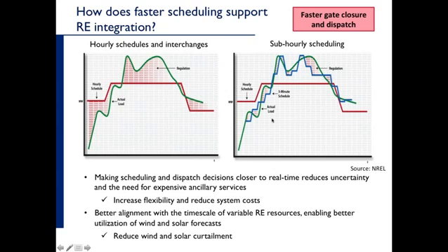Well, typically, the 5-minute economic dispatch is based on a forecast of the middle point of the 5-minute time period. And we talked through that on the timeline a few minutes ago. So, for example, we have a point right here where my arrow is. And we take a system snapshot, or we've already taken a system snapshot. We calculate the new dispatch point, and you can see we move from one dispatch point to another.